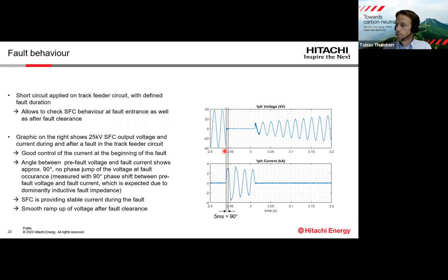The first line here shows the peak voltage before the fault. The second line shows the peak current during the fault, and there is roughly 5 milliseconds in between, and that indicates this 90-degree phase shift that we want to have. What we can also see is that after the fault, the SFC slowly ramps the voltage back up to nominal.